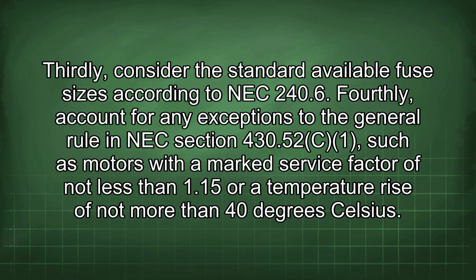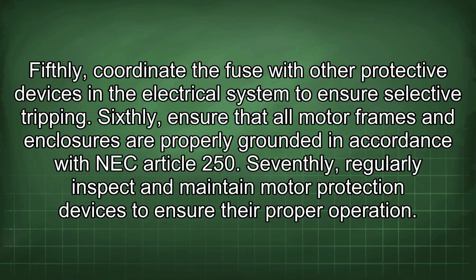Fourthly, account for any exceptions to the general rule in NEC section 430.52, such as motors with the marked service factor of not less than 1.15 or a temperature rise of not more than 40 degrees Celsius. Fifthly, coordinate the fuse with other protective devices in the electrical system to ensure selective tripping. Sixthly, ensure that all motor frames and enclosures are properly grounded in accordance with NEC Article 250. Seventhly, regularly inspect and maintain motor protection devices to ensure their proper operation.